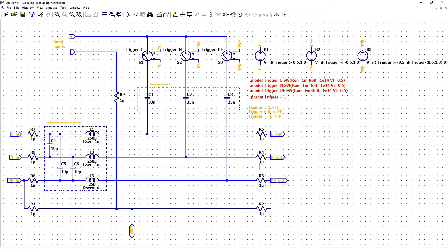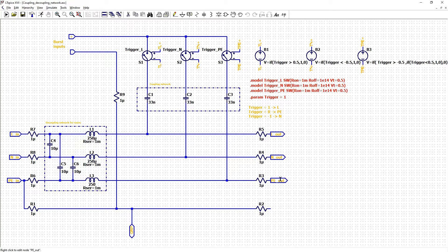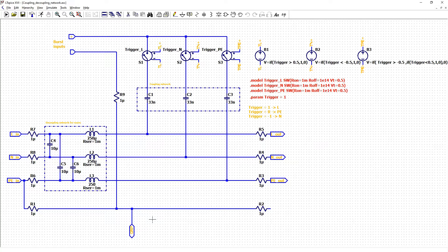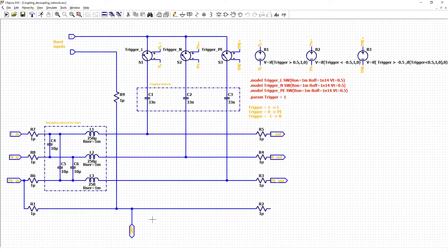Outputs for our DUT line neutral protective earth. And also ground reference plane because this is common mode signal that we will test and our coupling decoupling network is put on the metal plate in reality.